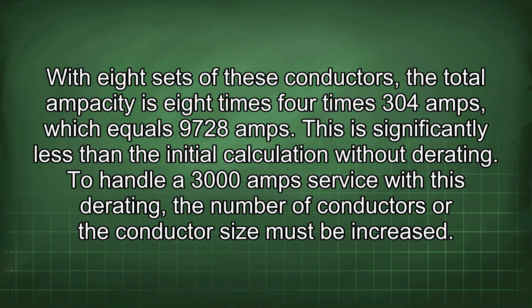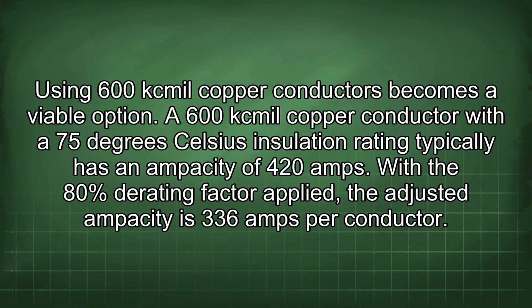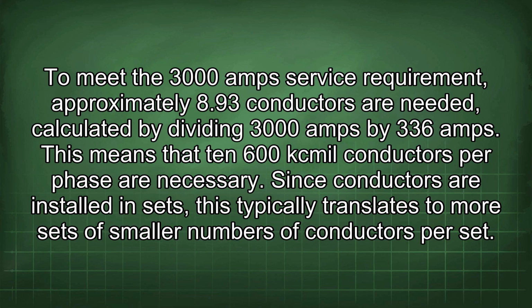To handle a 3000 amp service with this derating, the number of conductors or the conductor size must be increased. Using 600 kcmil copper conductors becomes a viable option. A 600 kcmil copper conductor with a 75 degrees Celsius insulation rating typically has an ampacity of 420 amps. With the 80% derating factor applied, the adjusted ampacity is 336 amps per conductor. To meet the 3000 amp service requirement, approximately 8.93 conductors are needed, calculated by dividing 3000 amps by 336 amps. This means that 10 600 kcmil conductors per phase are necessary.